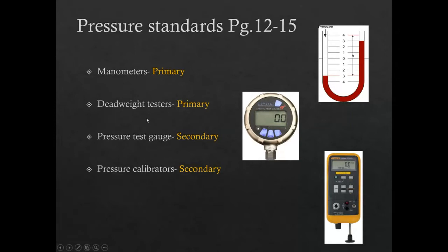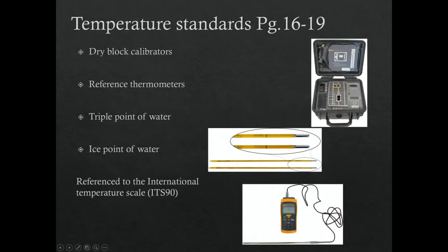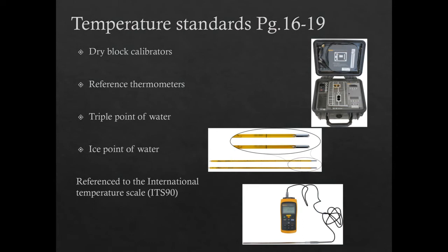A general guideline: if a standard has to be calibrated regularly, it's probably a secondary standard; if it only has to be calibrated occasionally or never, it's closer to the top and more likely a primary standard. Temperature standards we're familiar with include dry block calibrators, reference thermometers, and RTD or thermocouple additions to electronic meters.